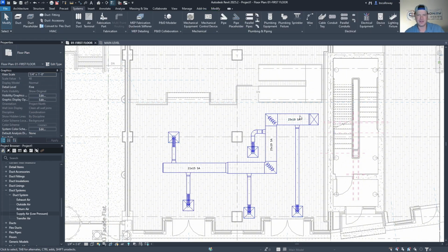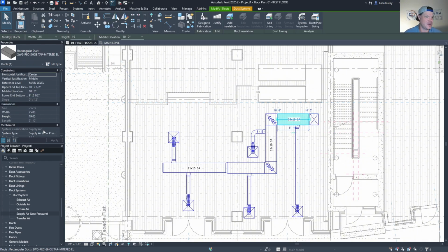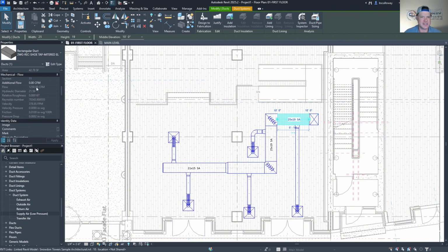When you select—this is very helpful for sizing ductwork, more on the engineering side. I think I use this more so than BIM, but sometimes in BIM I have to do this as well. If I click on this duct right here, that's going to give me all my properties under mechanical flow. You can see that this duct right here is carrying 1,250 CFM total, including all of these 250 CFM diffusers.